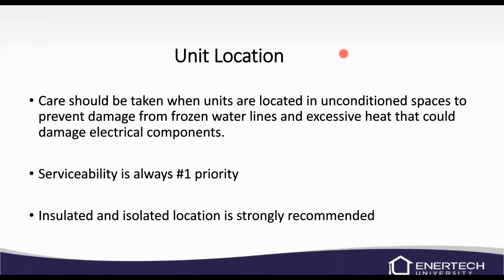Unit location. Make sure we don't like them located in unconditioned spaces. You can have excessive heat, humidity, frozen water lines, things like that. So we'd like it to be stored in a conditioned space. Serviceability is always priority number 1. If you ask an installer, that's not the priority, but at some point in the life of this equipment, it will have to be worked on. That's just the way equipment is. So you're going to have to be able to get around the unit and get the doors open and work on the unit.